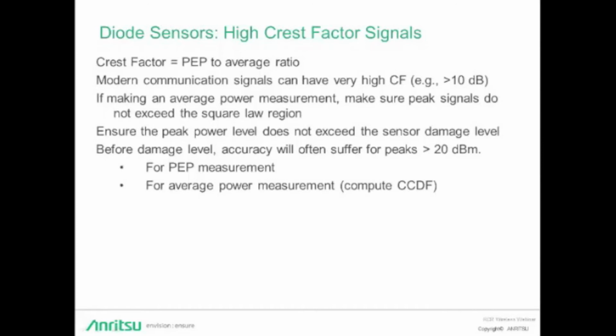When making a peak envelope power measurement, peaks above 20 dBm, a common top end of the measurement range for diode sensors, can be clipped, resulting in an inaccurate PEP measurement. Peaks above 20 dBm may be less of a factor on an average power measurement. It depends on the percentage of time the peaks are above the range. So the complementary cumulative distribution function, or CCDF, is a computation of the amount of time the signal spends above the average power level of the measured signal. So many power meters include that CCDF computation as part of their feature set.